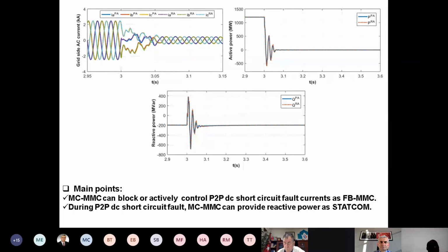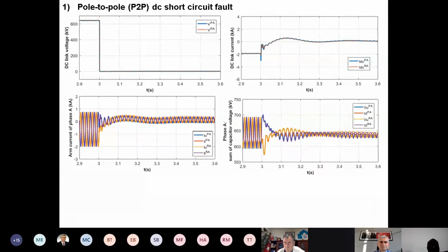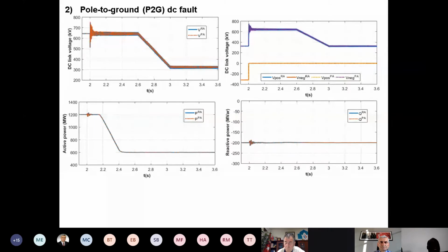And here is the pole to ground. But here I want to demonstrate a very important feature we call pole restraining. You can see here at this point a pole to ground fault happened, and this is the plot for the positive pole to ground and negative pole to ground, and you can see the fault happened at the negative pole. So the negative pole dropped to 0, and the fault shifting happened because of the asymmetric nature of the converter. So the healthy pole jumps to full VDC.